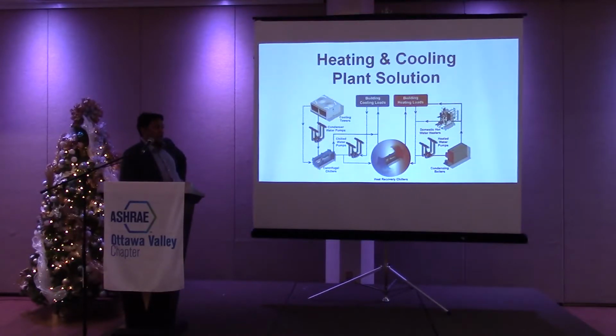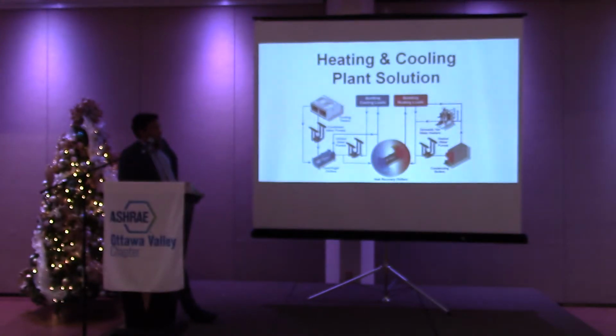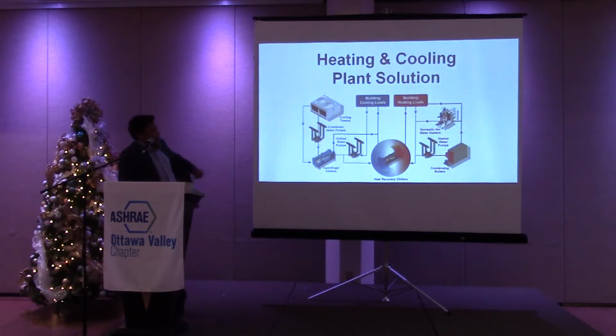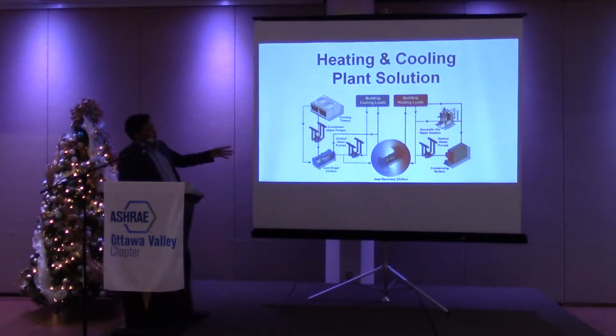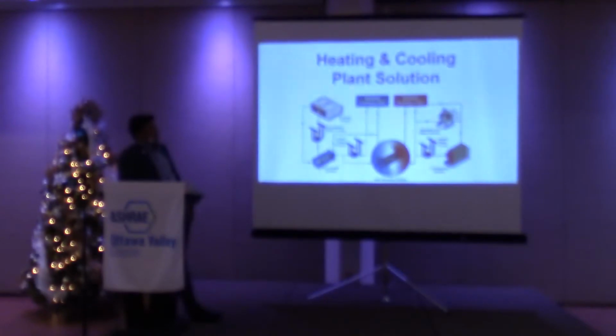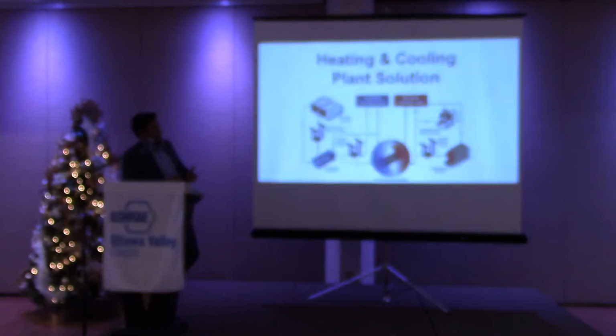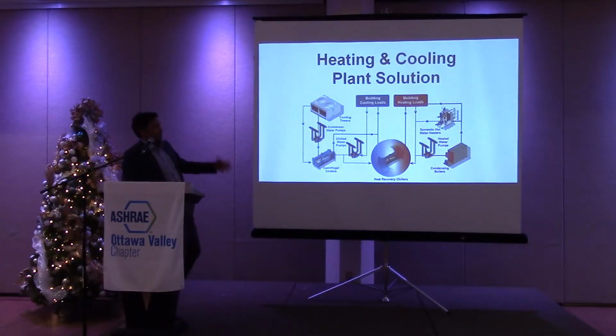It obviously is higher in the wintertime because we were doing airside heating, so we'd use that air also to heat the space, but in the summertime you still had a baseline reheat coil. So instead of burning gas in our boilers to heat in the summer, what we did was we stuck in heat recovery chillers, and ASHRAE 90.1 mandates that. So we're providing chilled water to all our 24/7 cooling loads, and the condensers on the heat recovery chillers are producing 130 degree Fahrenheit heating water for all our reheat coils. This entire building, the air handling systems, and all the heating systems and reheat coils were all designed for 130 degrees Fahrenheit with a 100 degree return.